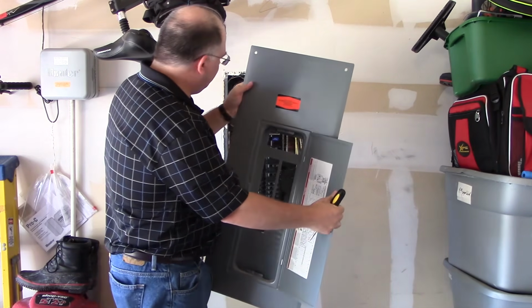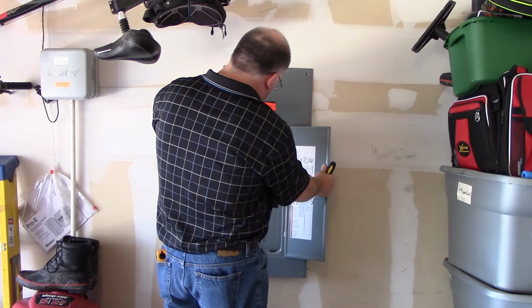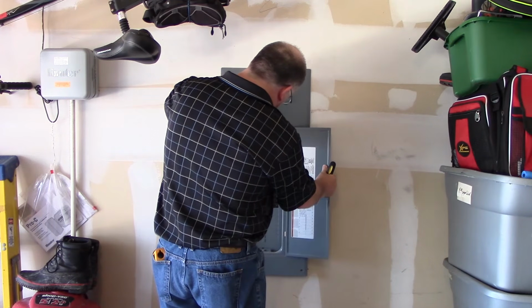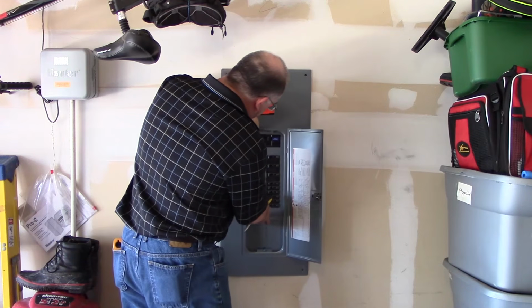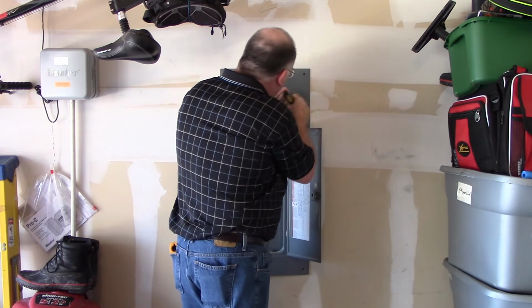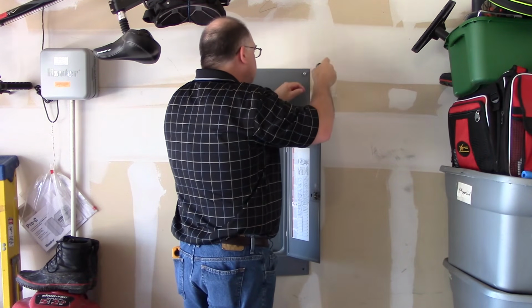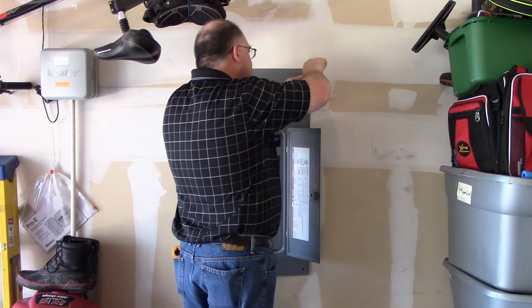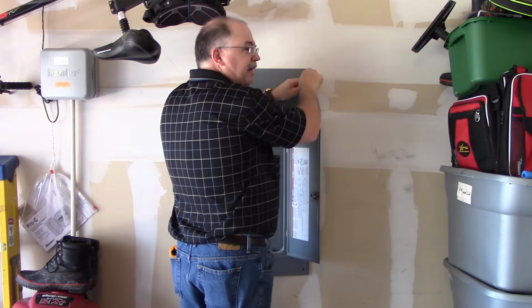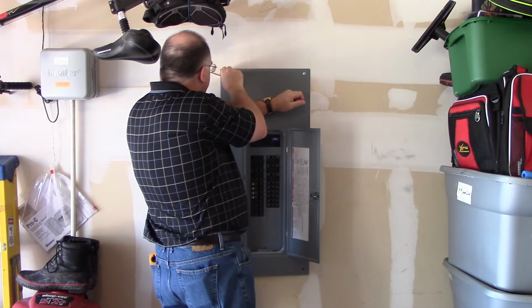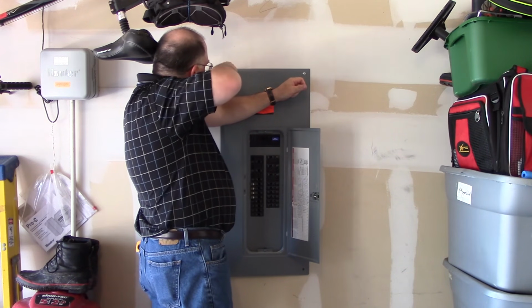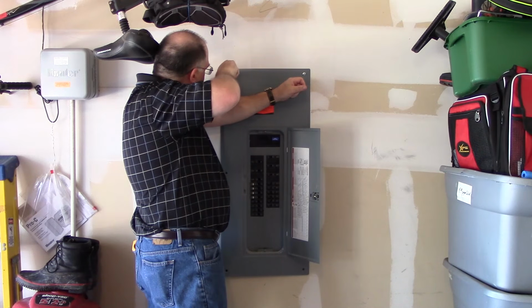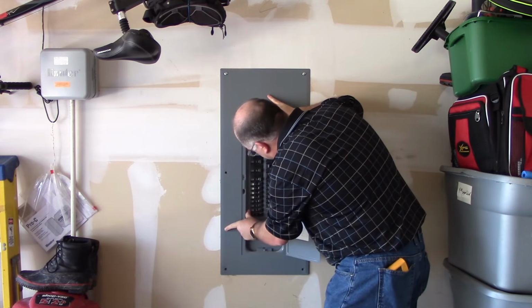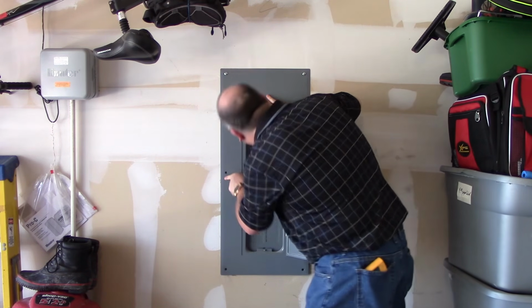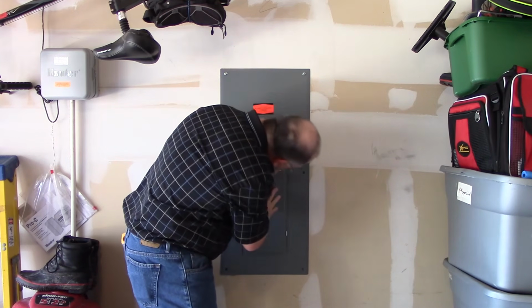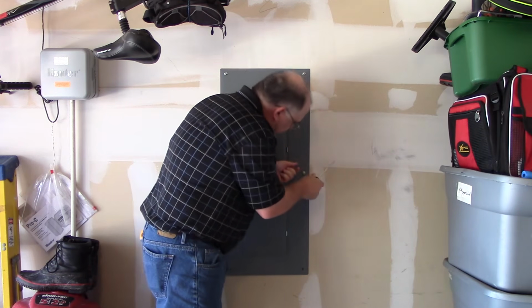Open up your cover so you can see it. Start up here. Kind of align it down so that it actually goes onto the main breaker first. Gets on there, and then make sure it's seated okay onto the panel. Look at your screws, and I'm going to install the first screw up at the top. Put that in. Again, I'm holding the panel with my left arm while I do it. I don't do it all the way tight so I can shuffle it around a little bit. So then I go to the left side and install that one. Okay. Alright, now I'm going to make sure everything looks good, everything's seated right in here. Line up those screw holes. Once it looks good, I'm going to shut the cover and proceed to put all of the screws back into this panel.